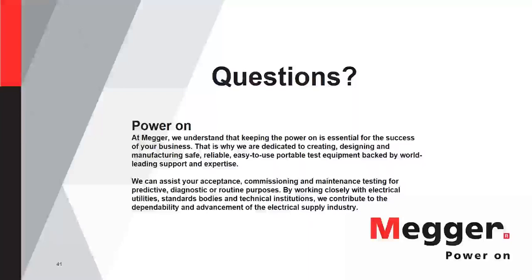The only thing I'd say is, if for some reason your testing equipment did trip, you actually are allowed one stop within your testing for either 10% of the total test time or 6 minutes, whichever is less. Generally with the testing, we usually end up being 6 minutes. So if you did have that, and you could stop it and go through and fix the issue within 6 minutes or 10% of the total time, you could continue the test if you needed to.